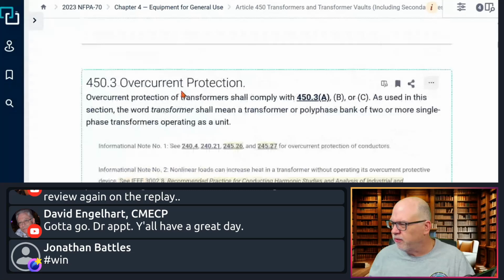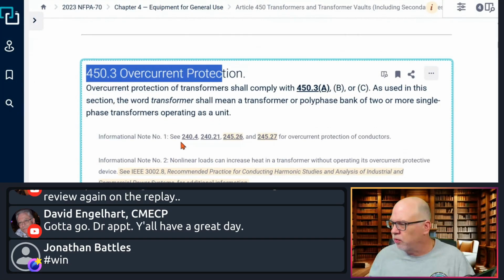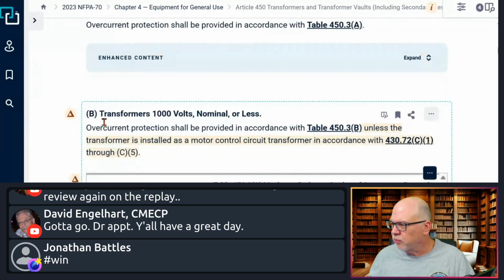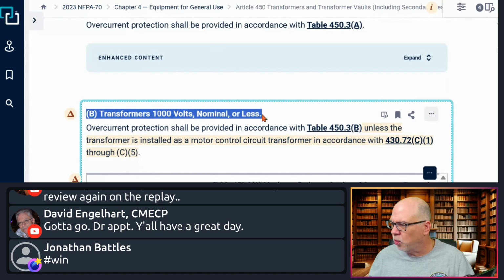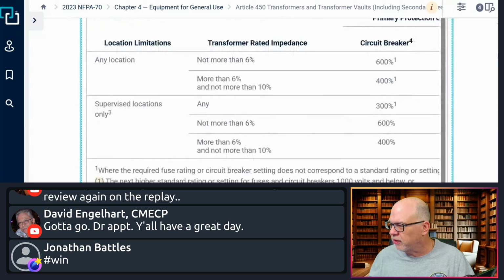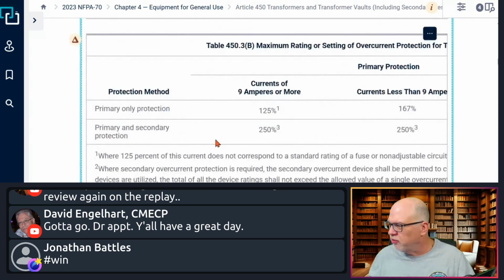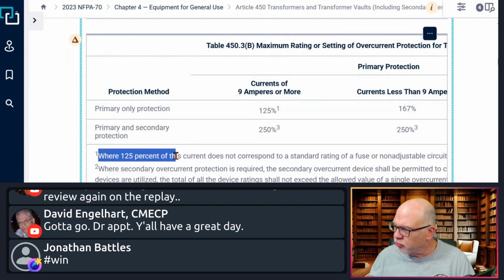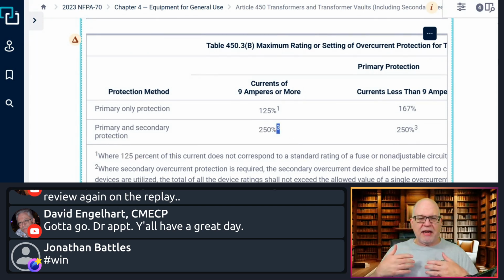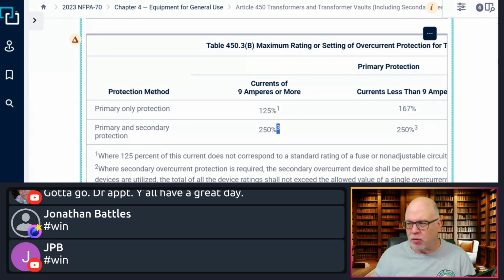So here's our 450.3, and we're dealing with probably this one here, transformers, 1,000 volts nominal or less, probably what you deal with most of the time. And we're going to be with this table down here, B, right? So you notice this one doesn't have the little asterisk number one, which is where the 125% is. This has a 3. So a 3 would allow us to possibly exceed the 250%, but that is dealing with special types of transformers. Okay?